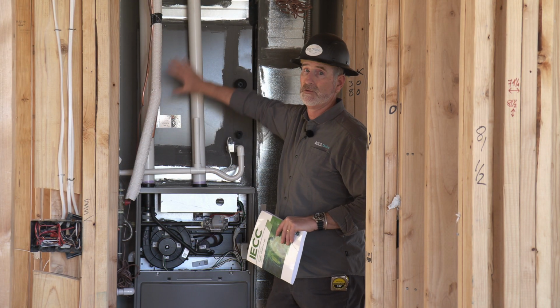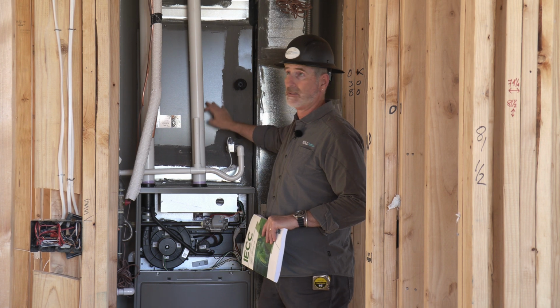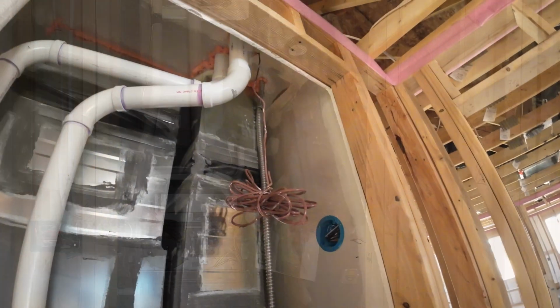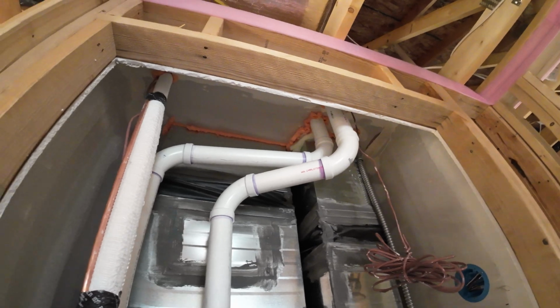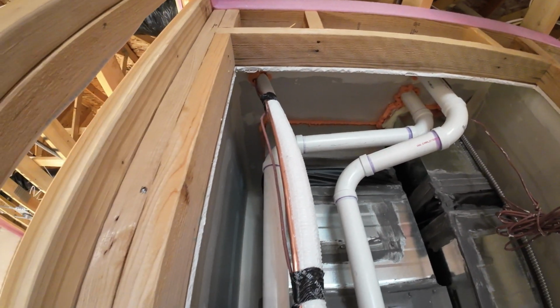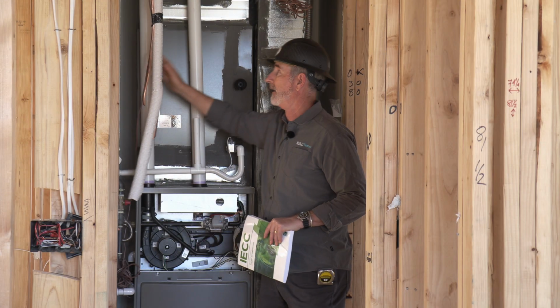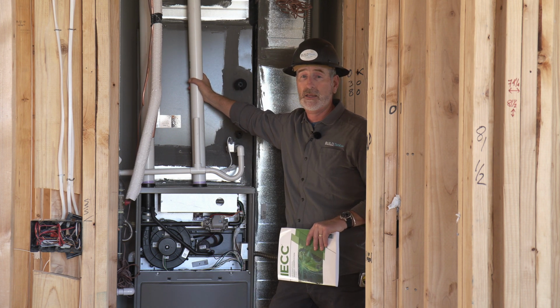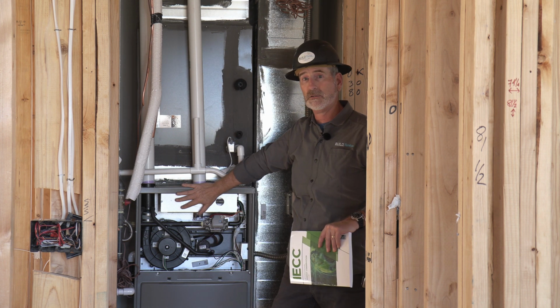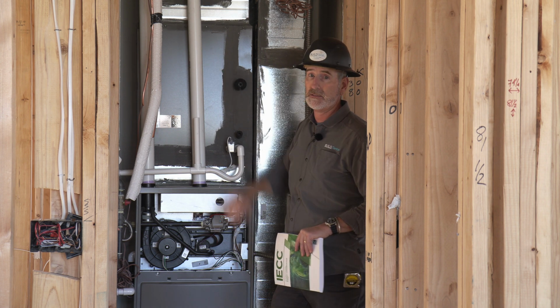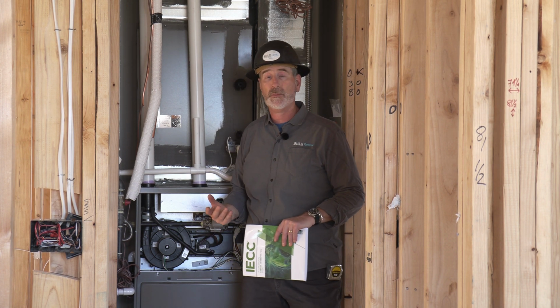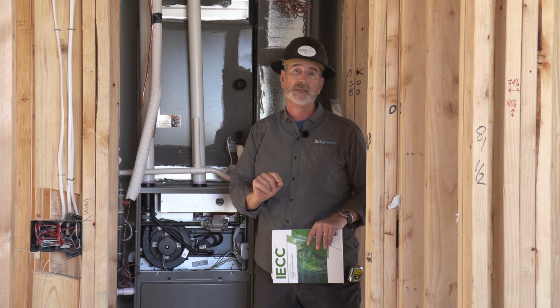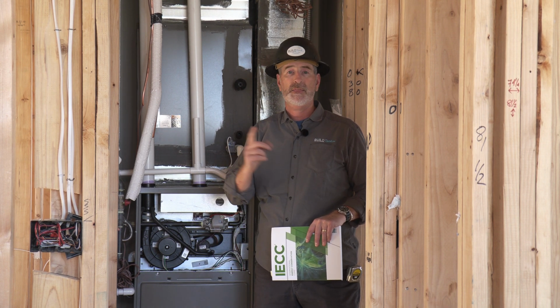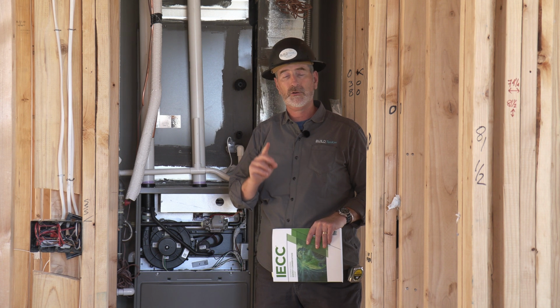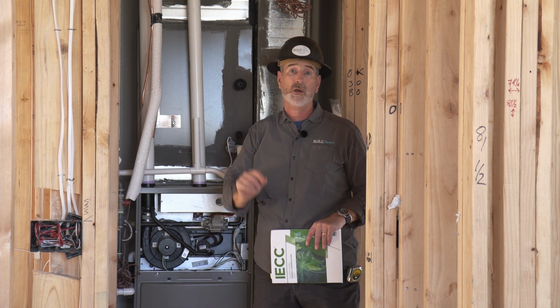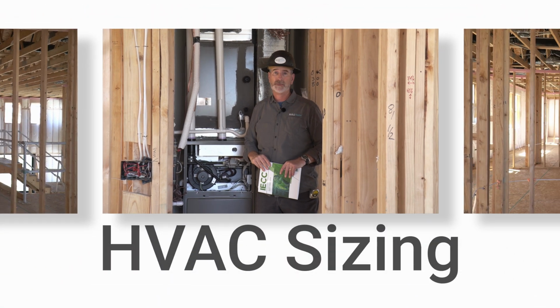So you can see the drywall here behind the duct system, and as they penetrate up into the attic, they've cut that drywall with right-sized holes that can be air-sealed well. Air conditioning lines, the venting and air intake for the sealed combustion furnace and for the duct itself here. So they've done a really nice job here, but it all goes back to sequencing. Get your air barrier up first, then cut the right size hole, and ideally you'll have one thing going through one hole so that you can air seal it properly.